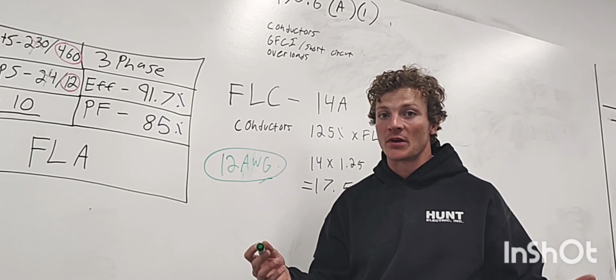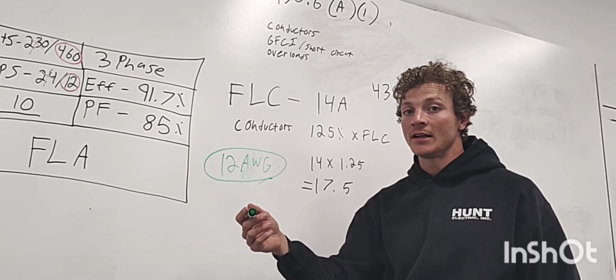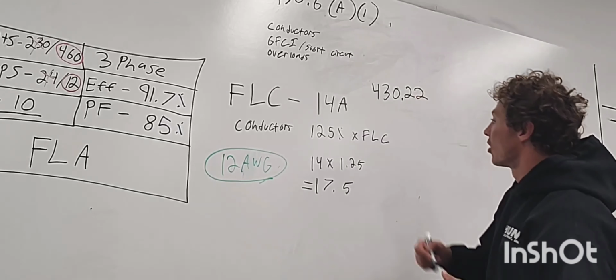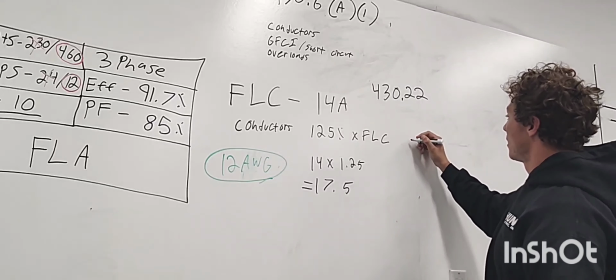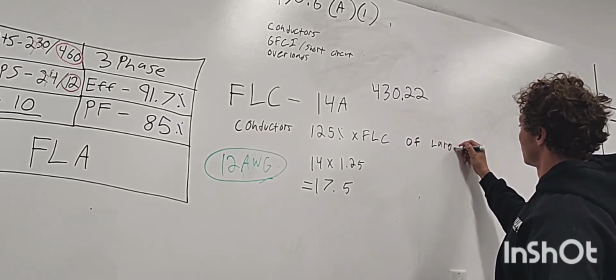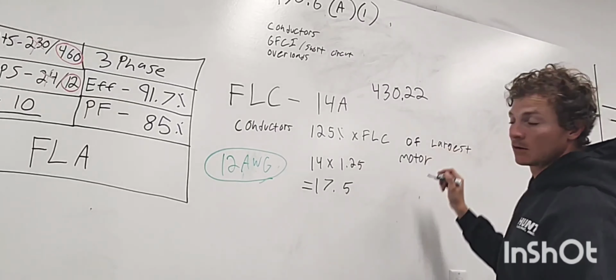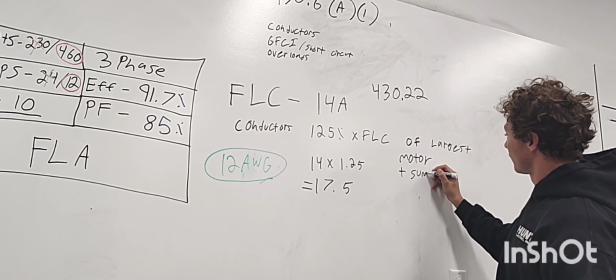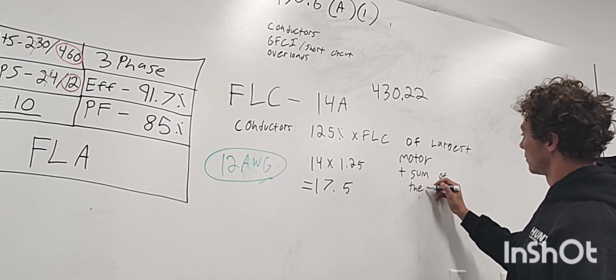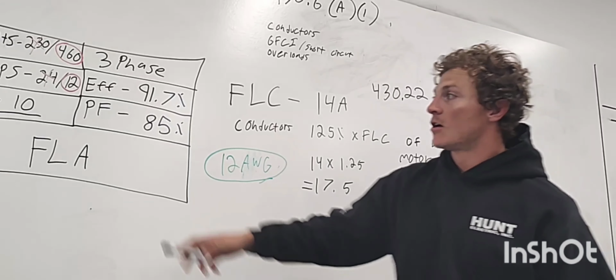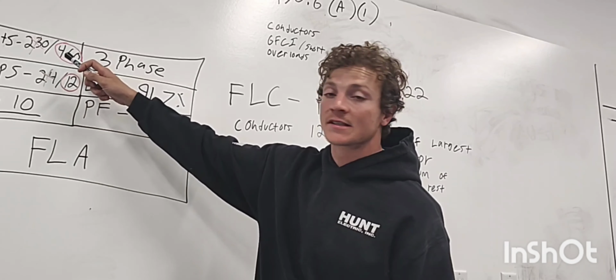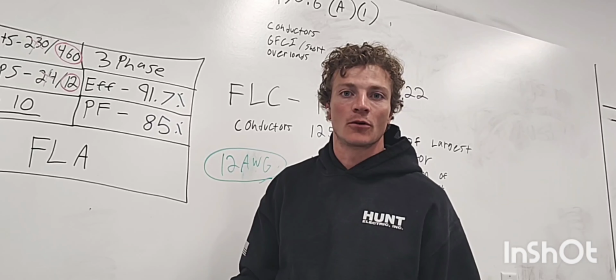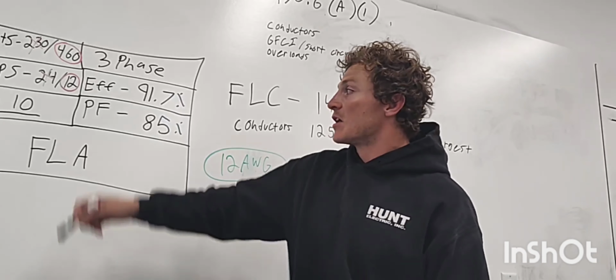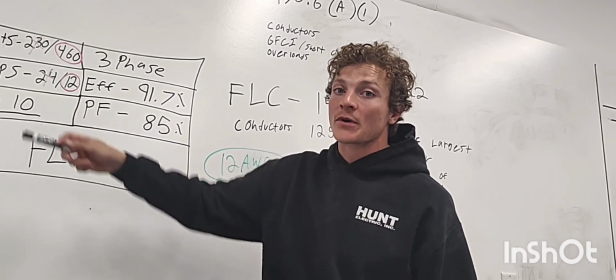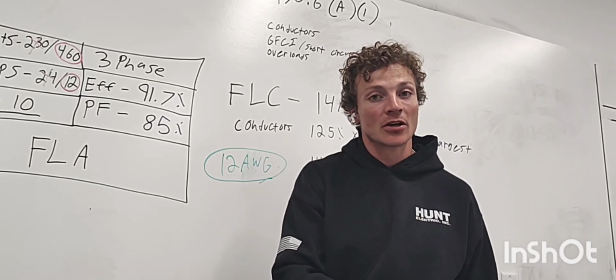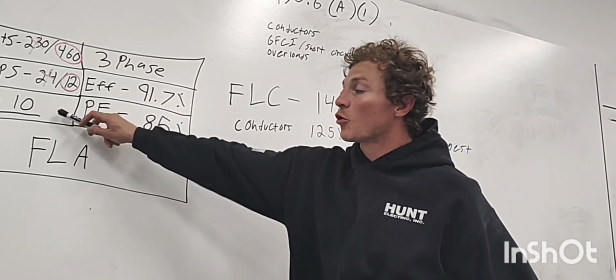If there was multiple motors being run, which I believe on the other one right across from it there is, what we would do is 125% of the FLC of the largest motor plus the sum of the rest. So if there was, for example, one at 10 horsepower, 460 volts, and then one at 8 horsepower, 460 volts, we just have to go off what the NEC says. This one could be rated at a higher horsepower, but it doesn't necessarily mean that it's higher amperage. So we have to look in the NEC. We can't use the nameplate.